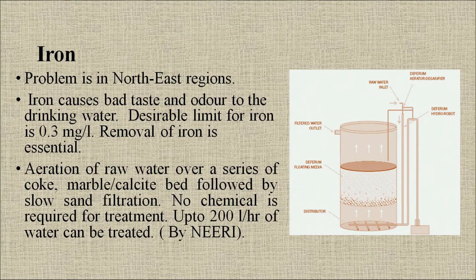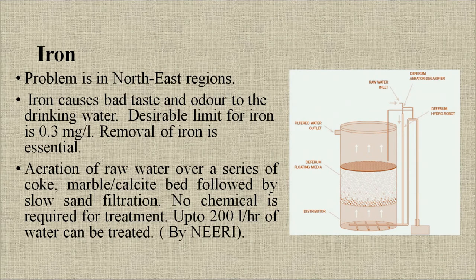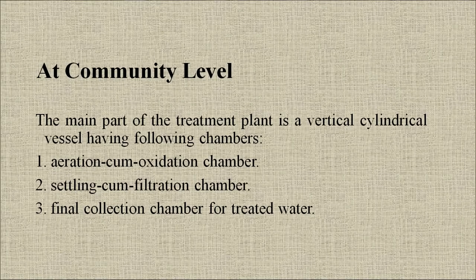Iron is mostly present in the North East region of India. It causes bad taste and odour in drinking water; the desirable limit is 0.3 mg/L. Removal of iron is done by aeration of raw water over a series of coke, marble and calcite beds followed by slow sand filtration. No chemicals are required and up to 200 liters per hour can be treated. At community level, the main parts of the treatment plant include an aeration-cum-oxidation chamber, a settling-cum-filtration chamber and a final collection chamber for treated water.